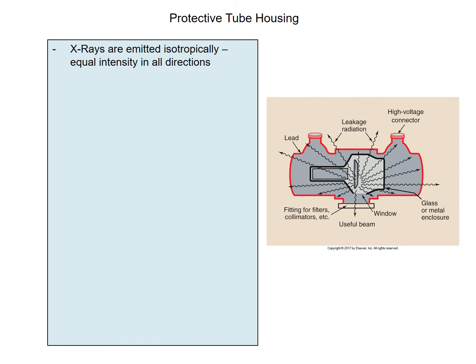Let's move into talking about the tube now. The protective tube housing. We want to keep in mind, if we look at this diagram over on the right, here you've got the tube, and the tube is enclosed in what we term the protective tube housing. We want to also keep in mind, and we can see this from the diagram, that when we create X-rays, the X-rays being created at the anode are emitted what we call isotropically. Remember, isotropically means with an equal intensity in all directions. So when we look at this picture here, we can see the photons are coming off not just where the useful beam would be utilized, but coming off in all different angles. We don't need those rays, so we'd like to contain those.